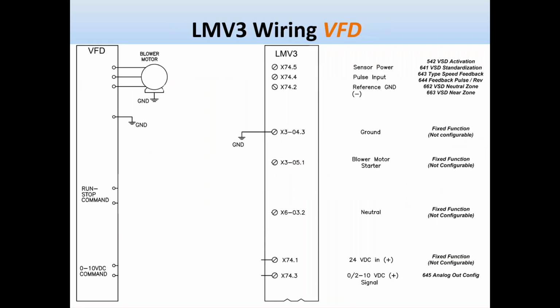The LMV3 can do a variable frequency drive. On the left, we'll see a variable frequency drive and the 3-phase blower and the terminals associated with it. In the center are the LMV3 terminals associated with the VFD, as well as descriptions on the right and all the associated parameters that are used to configure those terminals. When you use a variable frequency drive on an LMV3, you'll have to provide some additional equipment. The first thing you'll need is a speed sensor and a speed wheel. This comes in a kit together. The speed wheel you see is asymmetric. The speed sensor would give the RPM of the burner or blower back to the LMV3 so that the air can be monitored by the speed of the VFD.